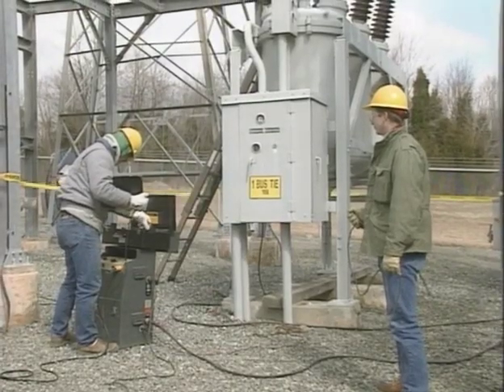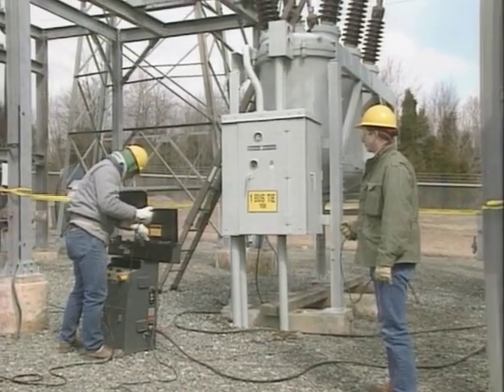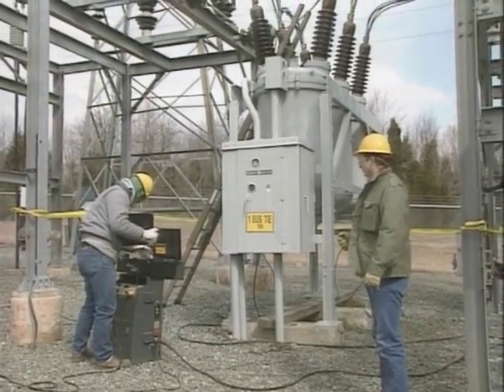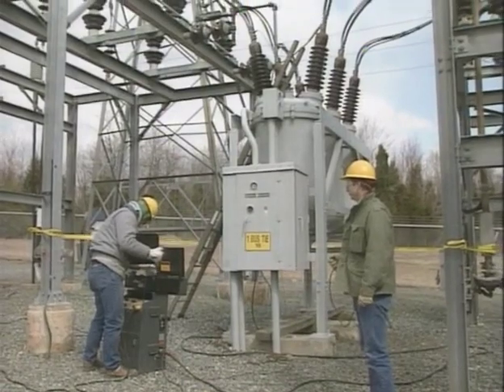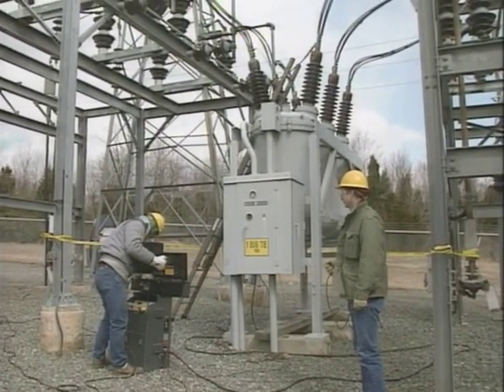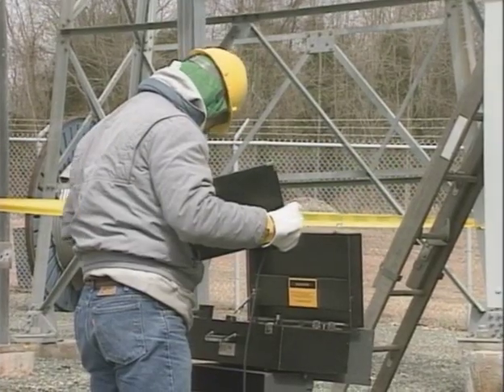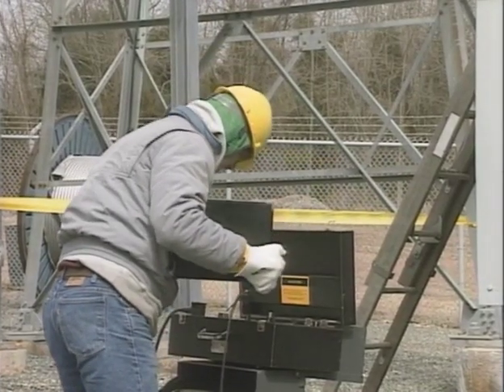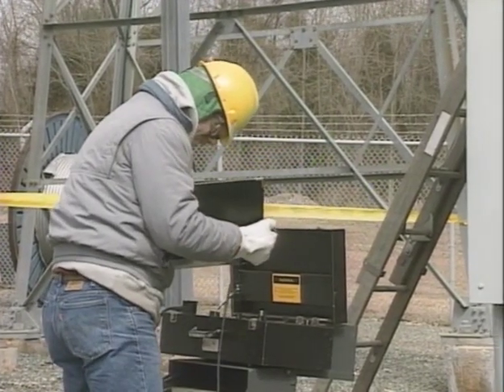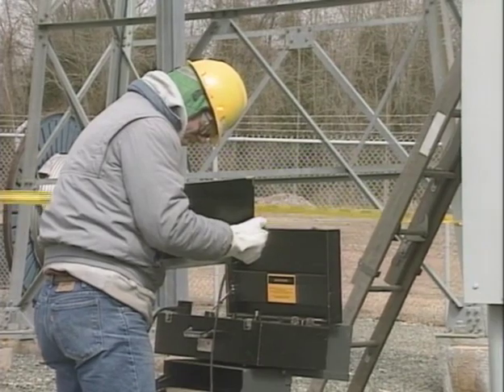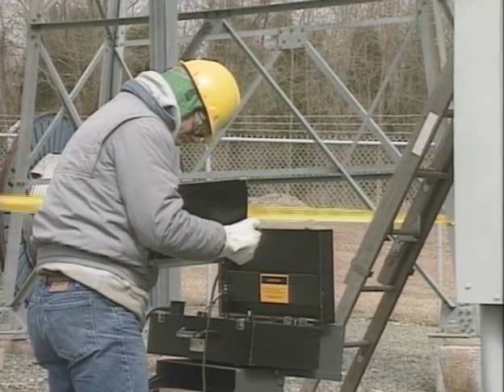If the power factor is not within an acceptable range, the breaker may have to be closely monitored or retested on a regular basis, or the bushings may have to be replaced. Regardless of the test results on the breaker, a power factor test is also typically performed on each of the bushings and on an oil sample if the circuit breaker is an oil breaker.